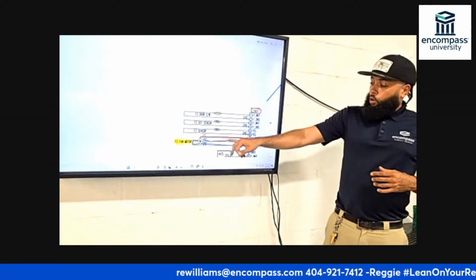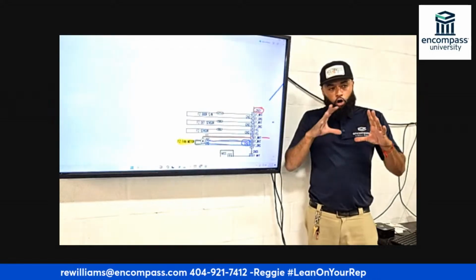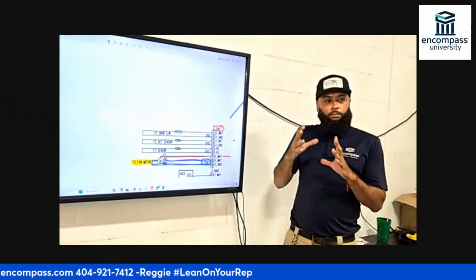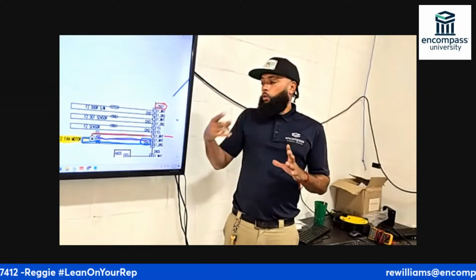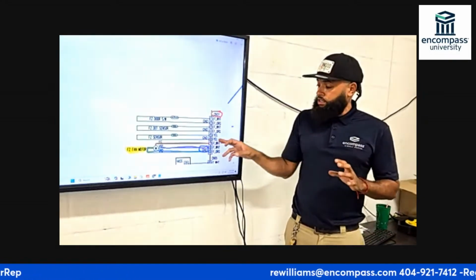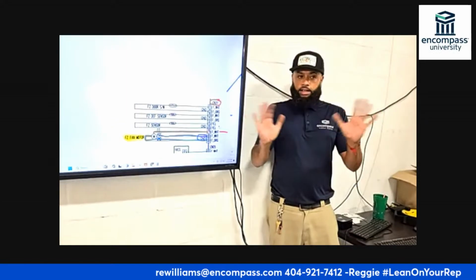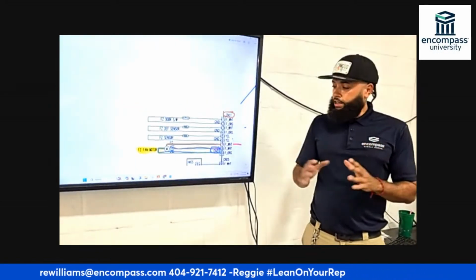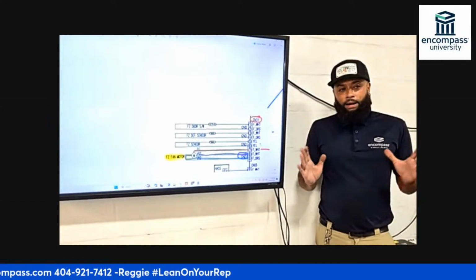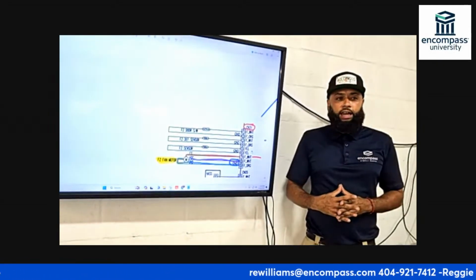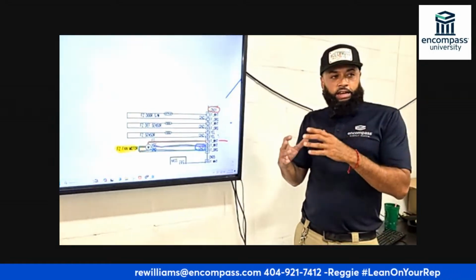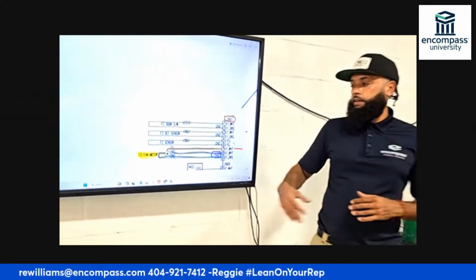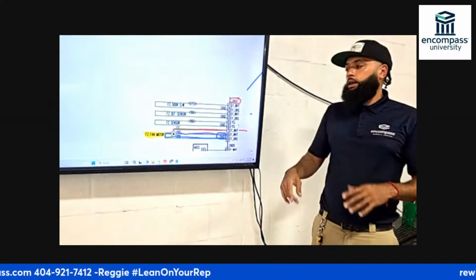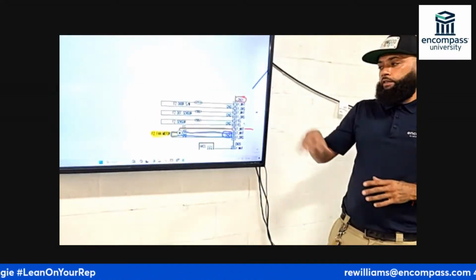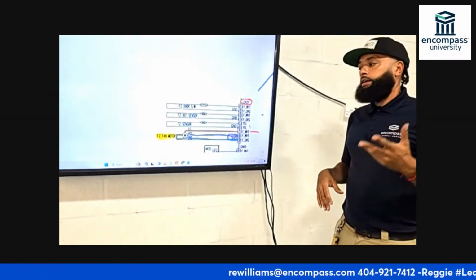But if that purple wire detects frost or an impedance, something preventing it from rotating, it will send a signal back to the board and say, let's stop sending voltage. Don't send any more voltage. And it will wait about 10 seconds. And then it will try to send the voltage again. After a few attempts of sending in voltage, when it realizes the blade isn't spinning, it's gonna give an error code. It's gonna give a fan error code.